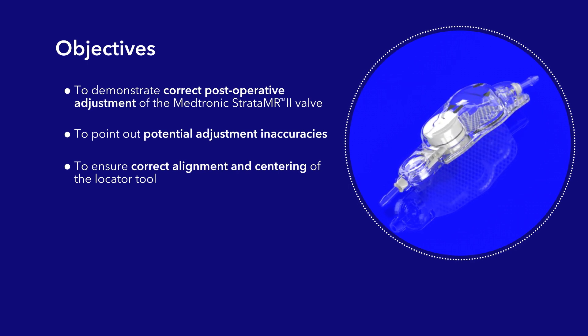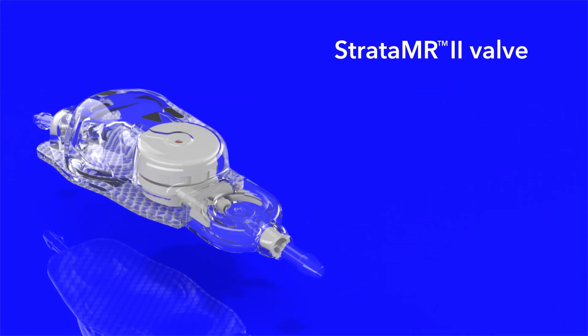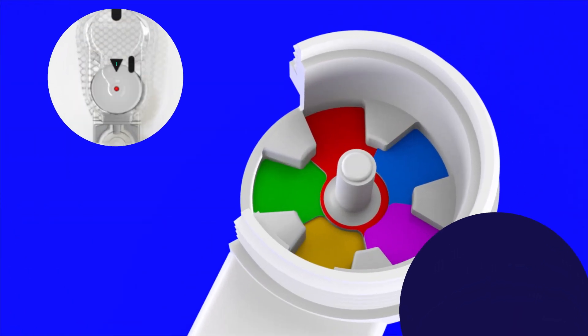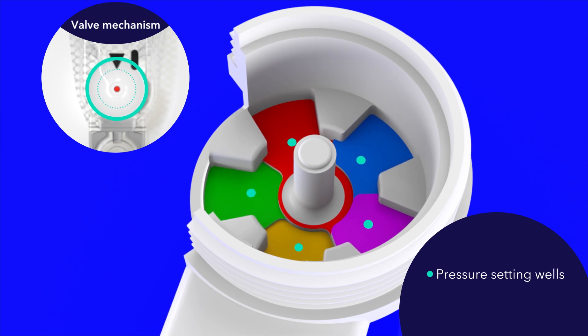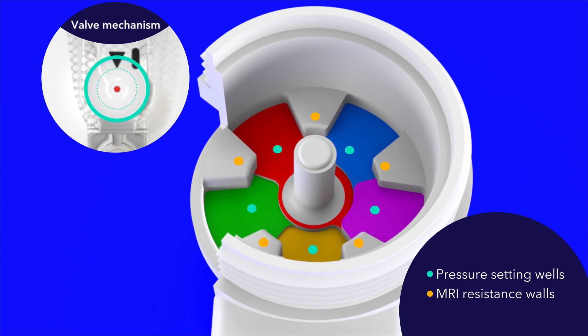The StrataMR II valve comes in two sizes: the StrataMR II Regular and the StrataMR II Small. Both valves have the exact same mechanism design. The StrataMR II valve is designed with five pressure setting wells separated by raised MRI resistance walls. These walls are designed to help maintain the performance level setting during MRI imaging.